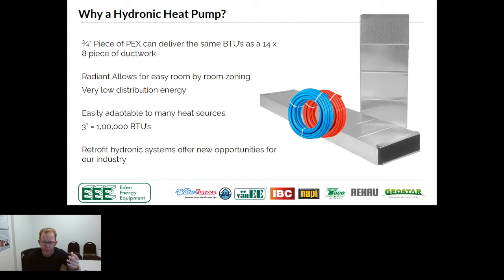We can deliver a lot of BTUs. We can do much more with a hydronic heat pump than we can with an air-to-air. But obviously, every application has its place. My feeling on hydronic heat pumps is that it's going to be a very small sub-segment of the market, but we're going to see that in the future, boilers are not going to be commonplace. We're going to be doing hydronic heat pumps. So it's important that we understand the technology, how to apply it, and some of the gotchas that are going to sort of catch us along the way.